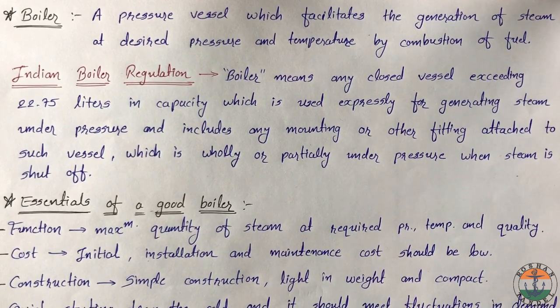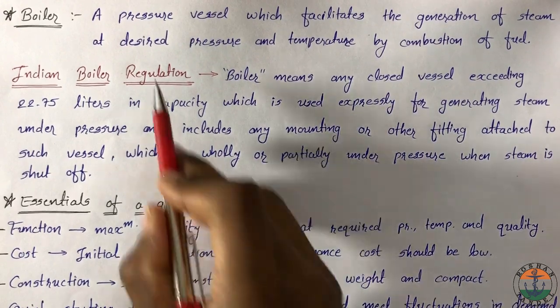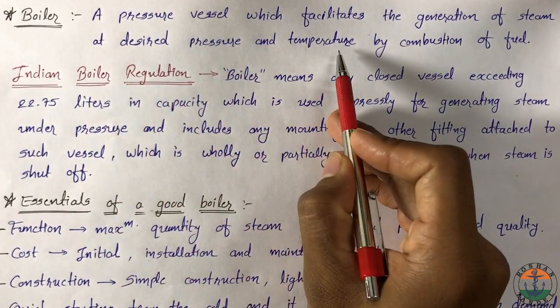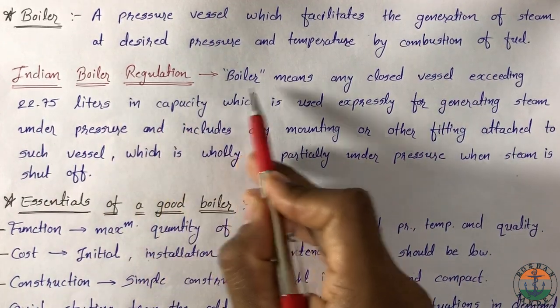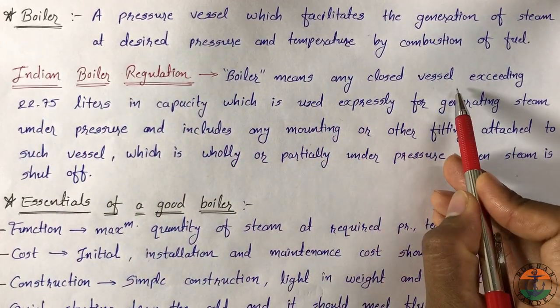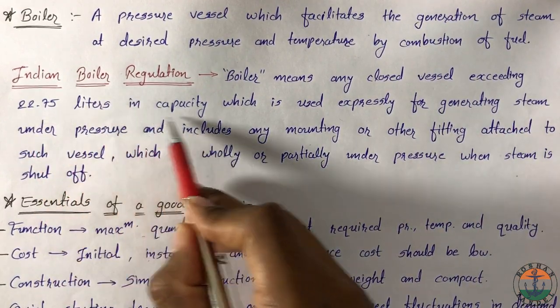A boiler is a pressure vessel which facilitates the generation of steam at desired pressure and temperature by combustion of fuel. According to Indian boiler regulation, boiler means any closed vessel exceeding 22.75 litres in capacity.